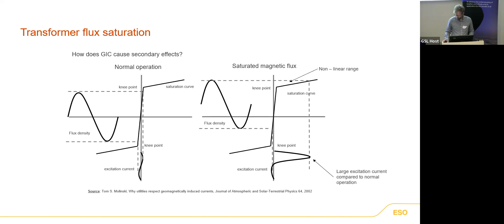So the GIC, which is a direct current, would push the magnetic flux into the non-linear part of that curve. So you can see on the right-hand side, we've got a saturated transformer where the magnetic flux is above the normal design parameters or the capability of that transformer core, and going into the non-linear region over the knee point. That causes you to have a very large excitation current, which you can see on the bottom of the graph there, a big spike.